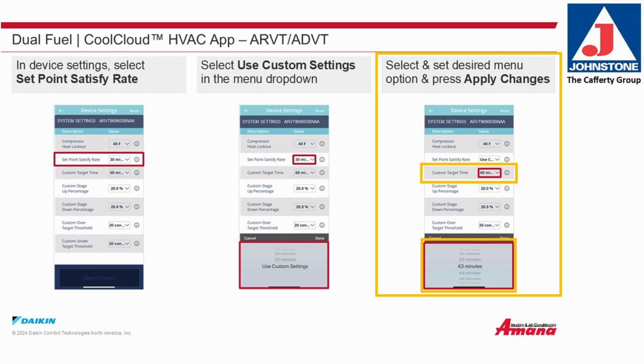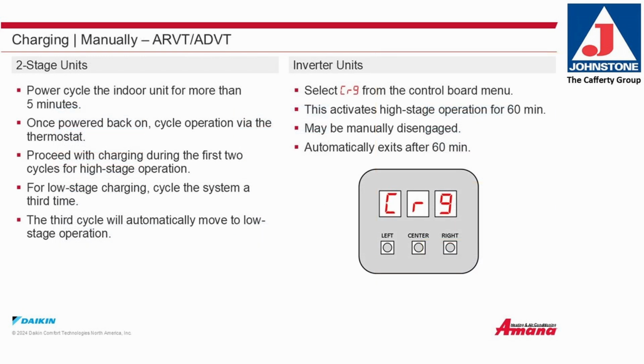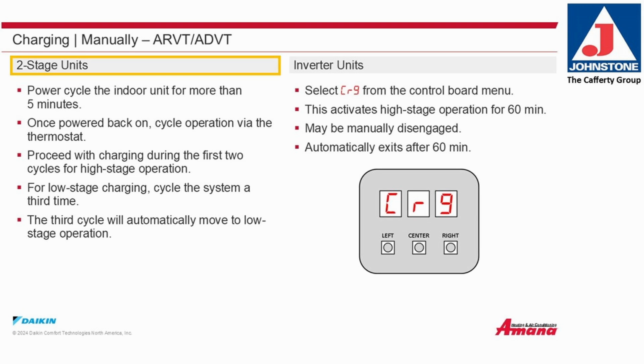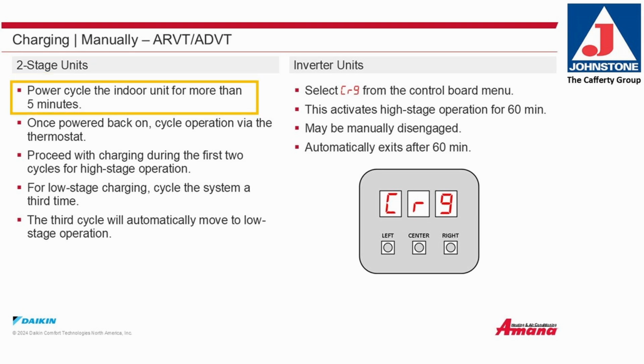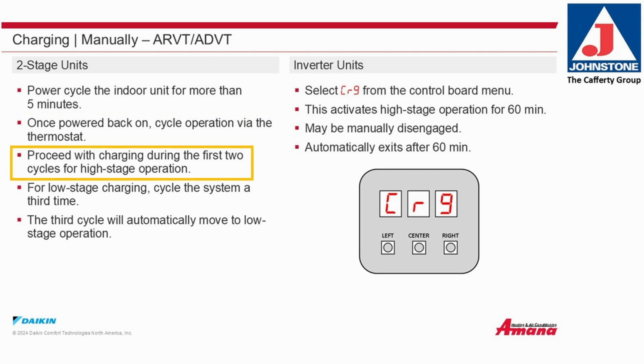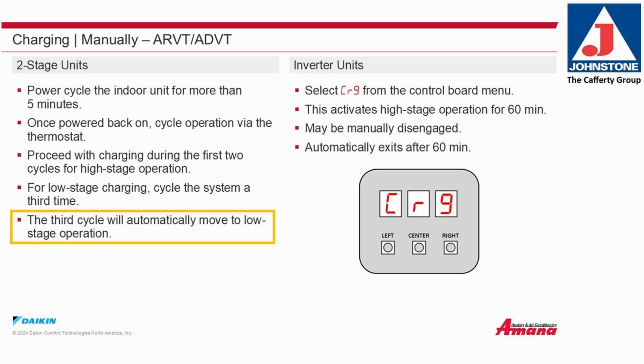Charging the system manually. For 2-stage units, power cycle the indoor unit for a minimum of 5 minutes. Once powered back on, cycle operation via the thermostat. Proceed with charging during the first 2 cycles for high-stage operation. For low-stage charging, cycle the system a 3rd time. The 3rd cycle will automatically move to low-stage operation.